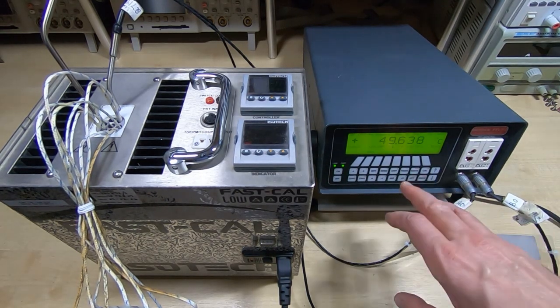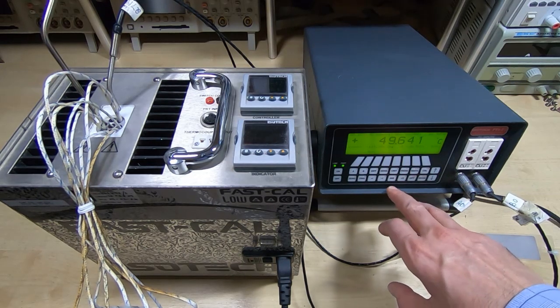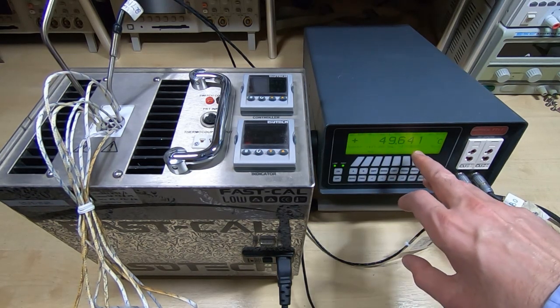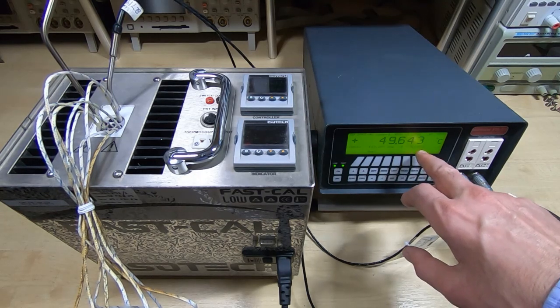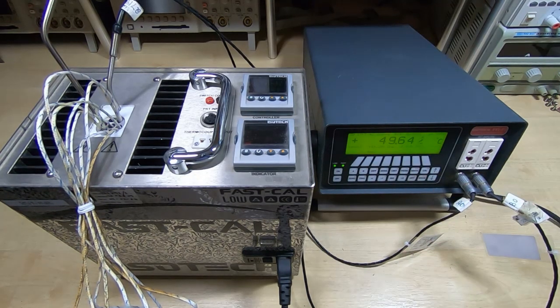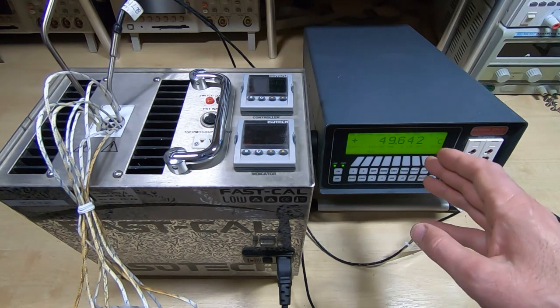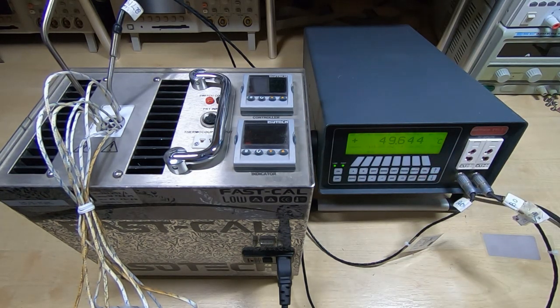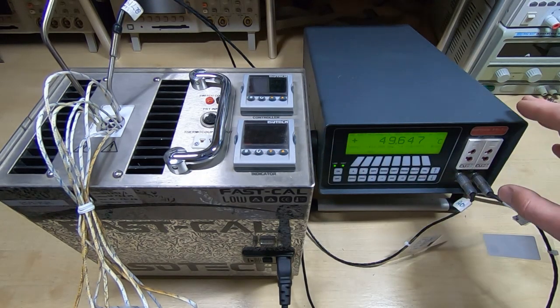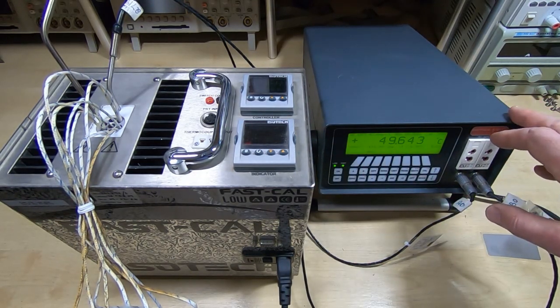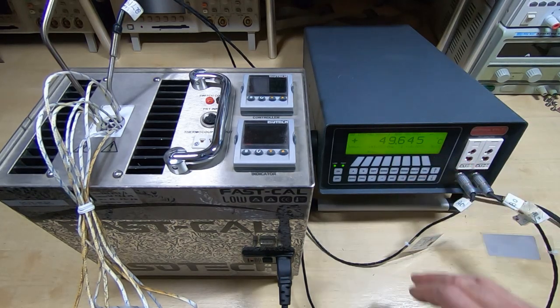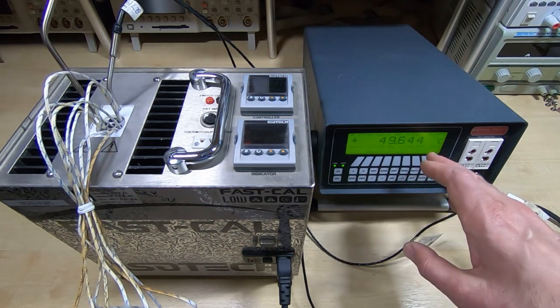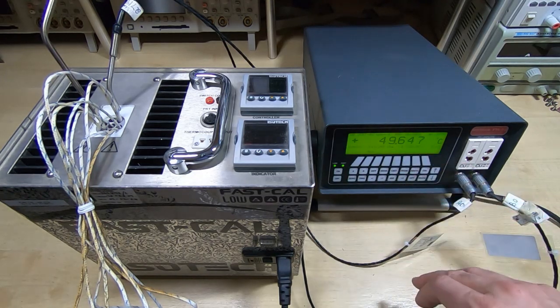Okay, so we're just settling on 50 degrees. I don't know if this display will actually come out on the video or not, but what I'm looking for is for the second digit from the right to stop changing rapidly. If it's changing less than once every 10 seconds or so, then for this application I would consider that settled. In a real world application that we normally use, we wait for the units to settle so it's not changing by the second least significant digit more than once every 2 minutes. But bearing in mind that's 1/100th of 1 degree centigrade, so it is a fairly precise reading.